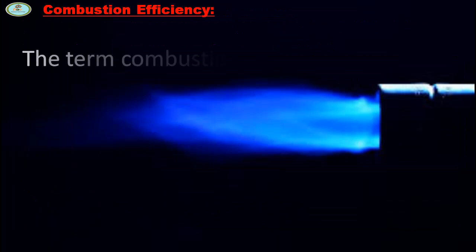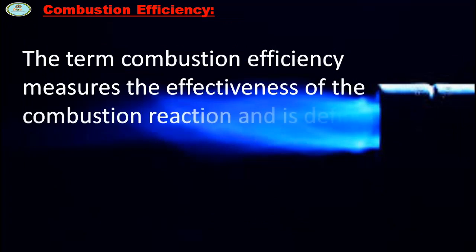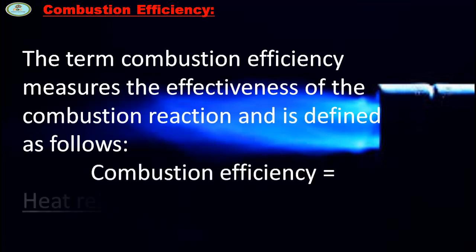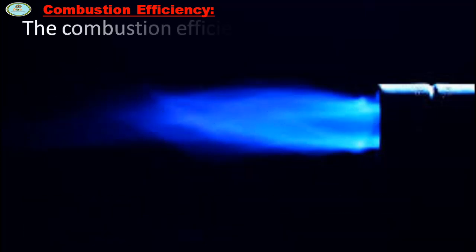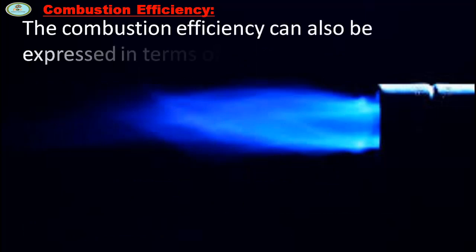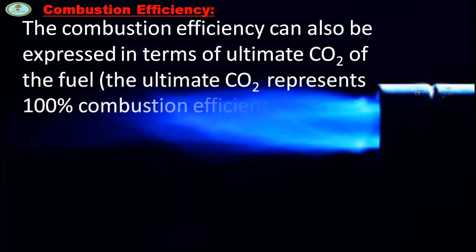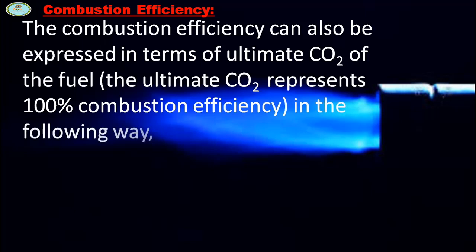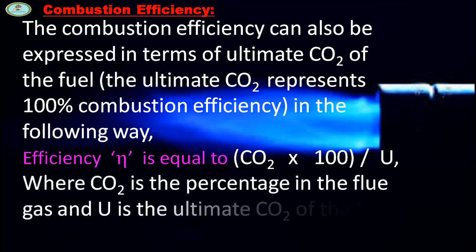The term combustion efficiency measures the effectiveness of the combustion reaction and is defined as follows: combustion efficiency is equal to heat released during the combustion divided by heat contained in the fuel. The combustion efficiency can also be expressed in terms of ultimate CO2 of the fuel. The ultimate CO2 represents 100% combustion efficiency in the following way: efficiency η is equal to CO2 × 100 divided by U, where CO2 is the percentage in the flue gas and U is the ultimate CO2 of the fuel.